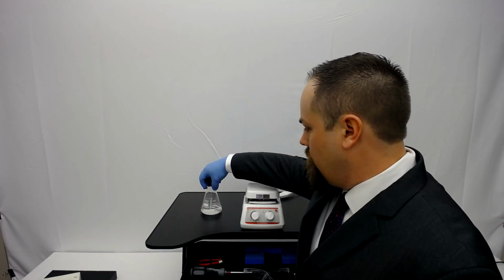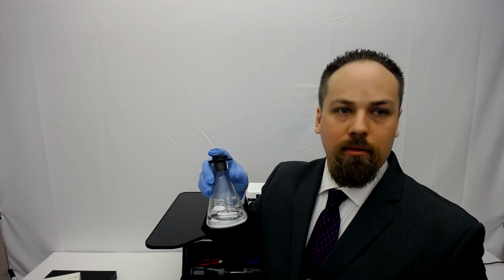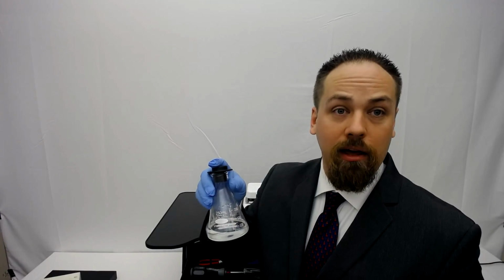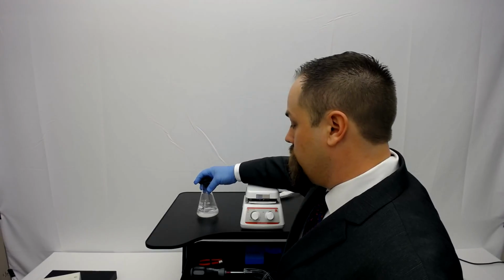So you can see here we have a fluid. As I said, I'm not going to be going through heating calibration today, but if you are working with a heating unit, make sure you're using an appropriate fluid. Today we have water, and for the stir calibration, we're using water, but water can boil away. There are certain silicone oils that can be used. Big consideration, if you do use a higher temperature oil, is to make sure that there is no moisture in it. If you're heating at very high temperatures, the moisture can boil before the oil does and cause a popping in the mixture. So make sure you're using the appropriate fluid for the temperature that you're working with.